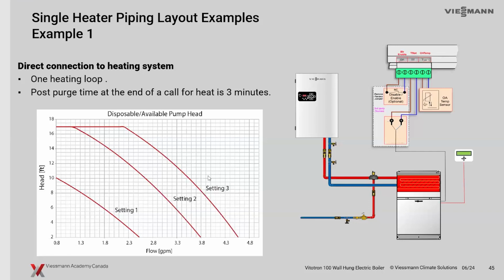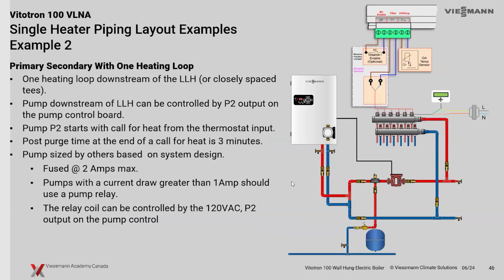As far as what pump speed I've got here, it's going to be a real good function of the pressure drop through this coil and the piping and which one we're going to set. And the nice thing is, of course, the unit itself will tell you what its flow rates are as you set that pump speed from 1 to 3, and you can dial it into a nice setting using the diagnostic tools on the boiler itself.